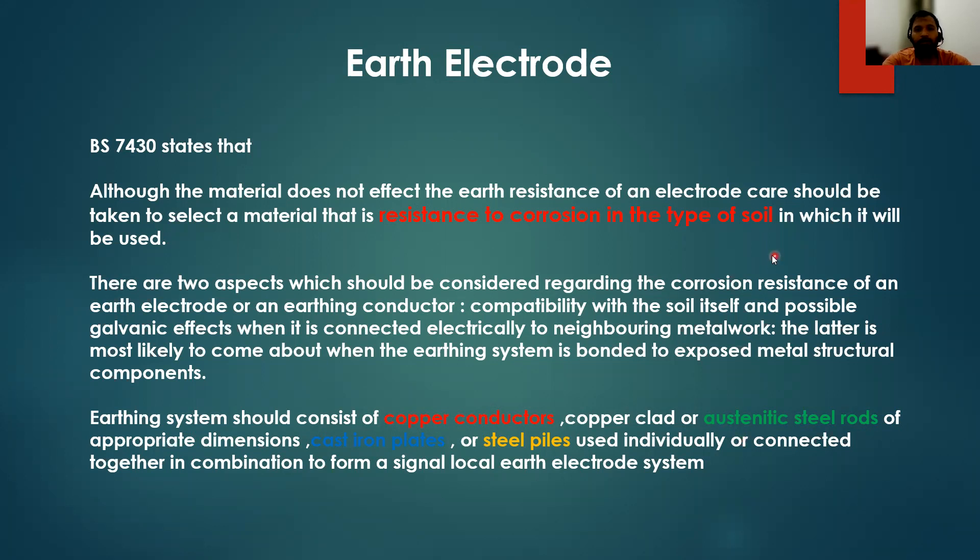The basic concept is it should have resistance to corrosion in the type of soil. The material, while you are choosing the earth rod, it should not be corroded. When earth rod is corroded, then there is no more protection because in the case of fault current, it should go through the ground area. But in this case, if your earth rod is corroded, there is no contact between your system and the earth. Basically, we have to be very careful while selecting the earth rods.